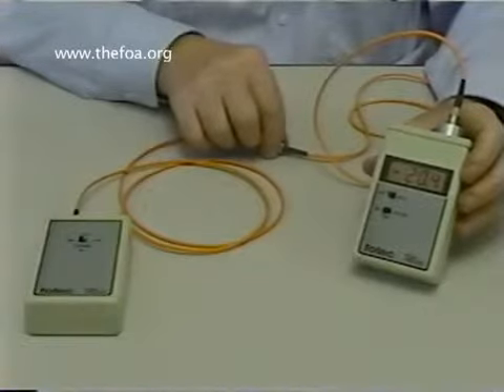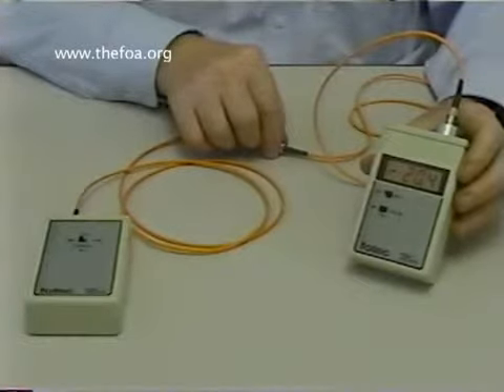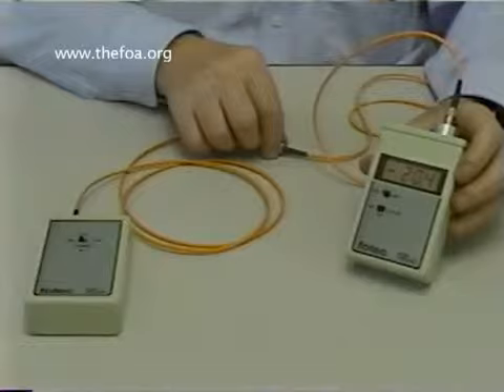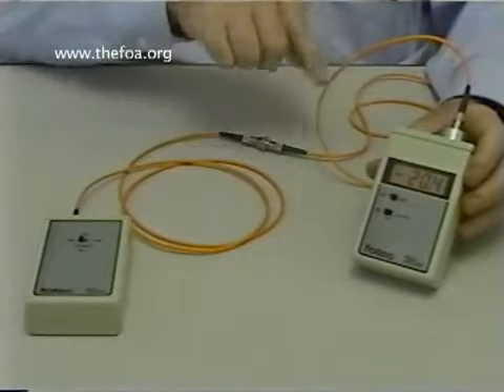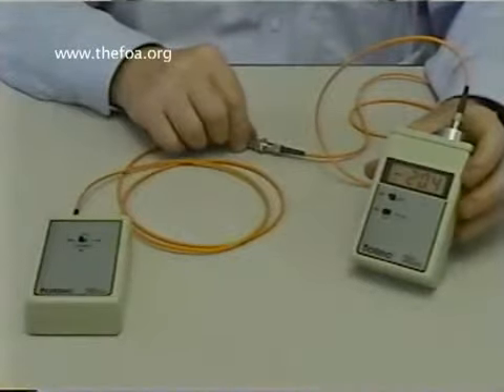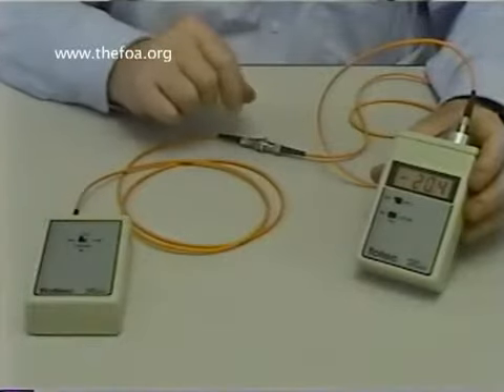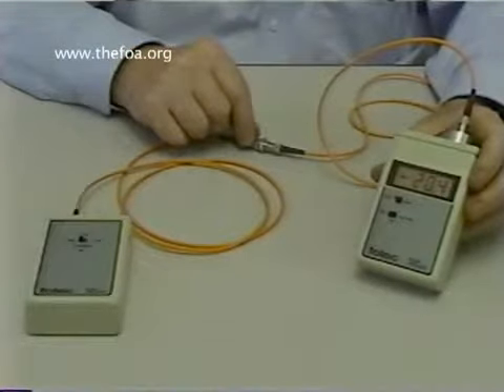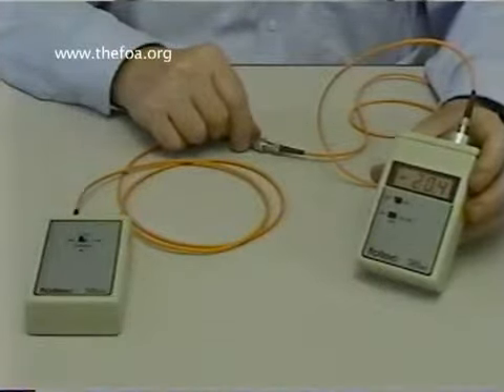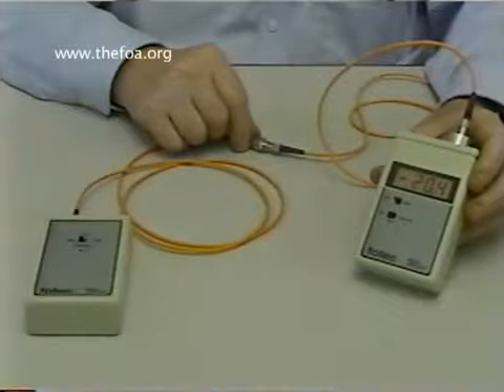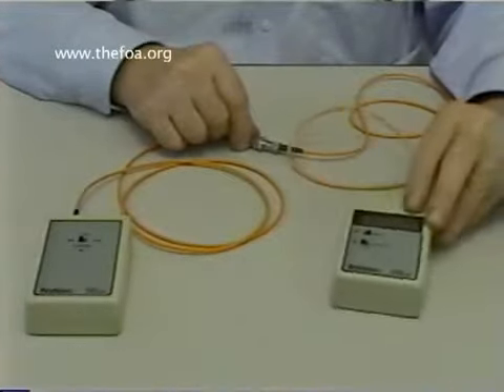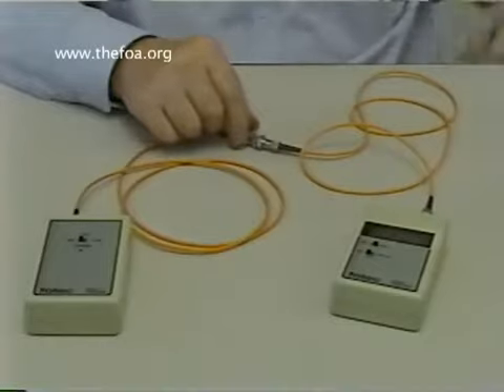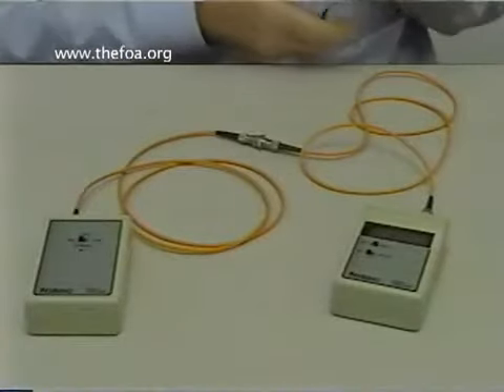This is very, very good when we're trying to troubleshoot bad cables. If we have a high loss cable and we test it this way, single-ended, we can tell if a connector on either end of the cable is bad, and which connector is bad is the one that we want to find and replace. So this is a powerful tool for actually troubleshooting what's bad about a fiber optic cable.